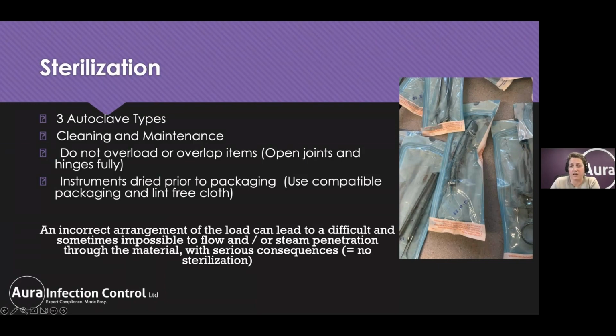So B, or vacuum autoclaves, can process any load: porous materials, products in pouches, textiles, hollow items, hand pieces, for example. And that's because type B, or vacuum autoclaves, use steam under pressure and achieve that pressure by using a vacuum. So they are active at sucking out the air from the chamber. By contrast, an N-type autoclave is designed for sterilizing simple materials. The N stands for naked solid products. Therefore, these autoclaves are used for solid items. They shouldn't be used for textiles, porous loads, hollow items. Even putting something in a pouch would present too much of a challenge for these types of autoclaves. So it's a weakness of these types of autoclaves that steam penetration cannot be guaranteed into lumened items.